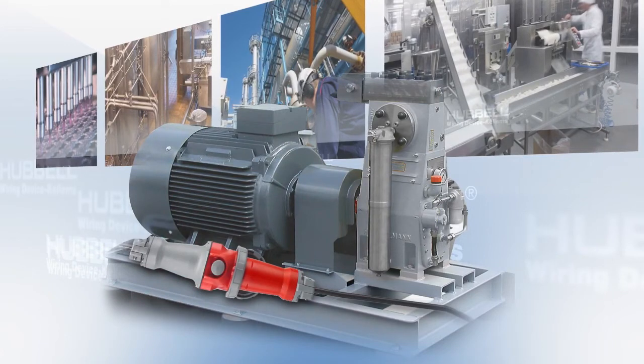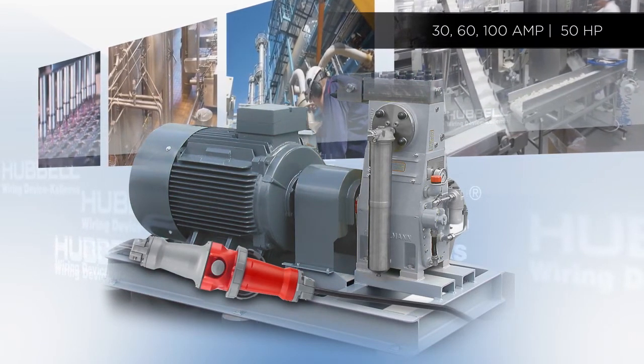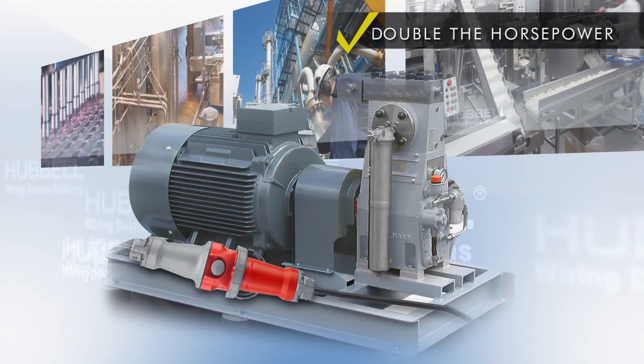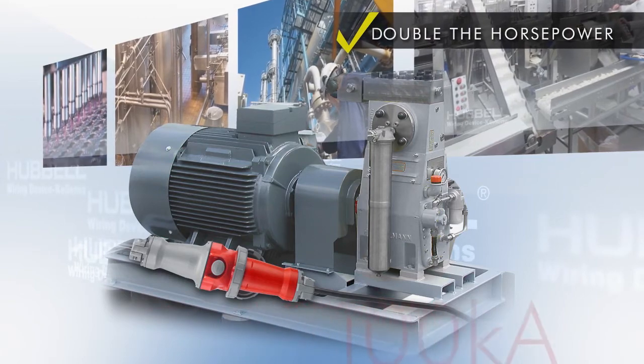The Advantage Series is now available in 30, 60, and 100-amp switched connector versions with a maximum horsepower rating up to 50. This is a new industry benchmark, nearly doubling the previous. In addition, it has a short-circuit current rating of 100 kA when used with a Class J fuse.